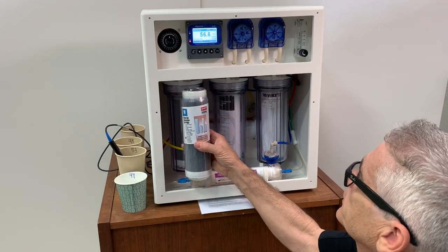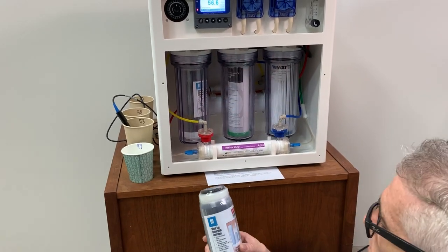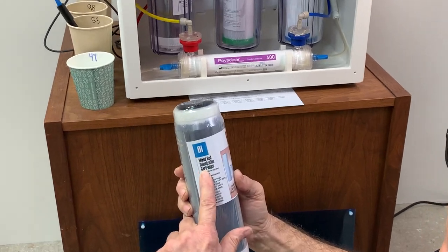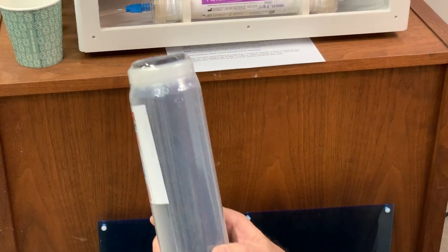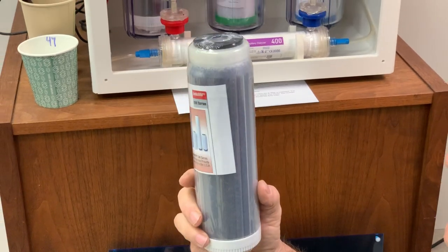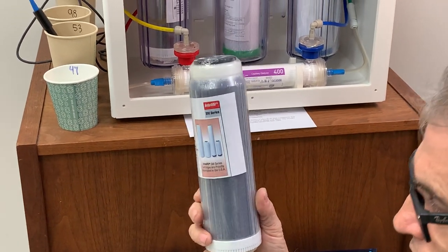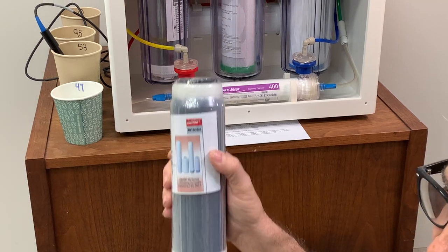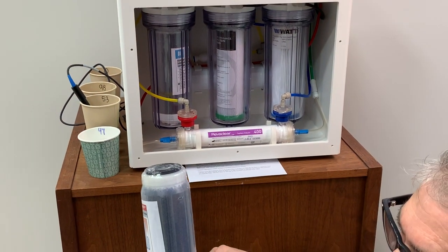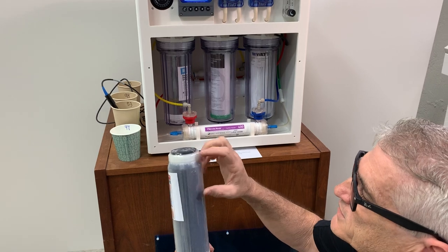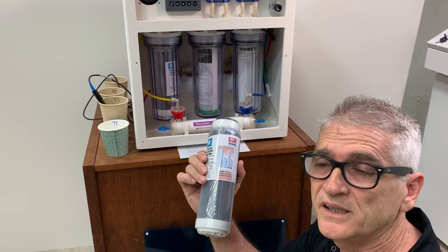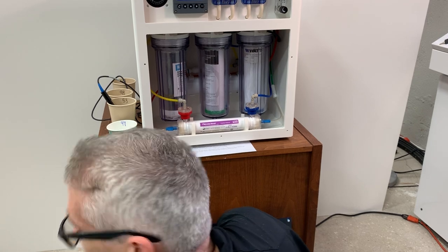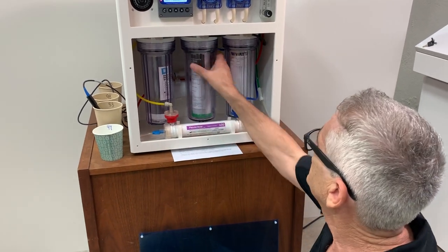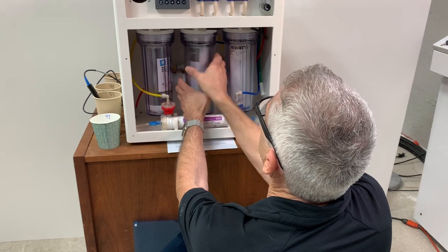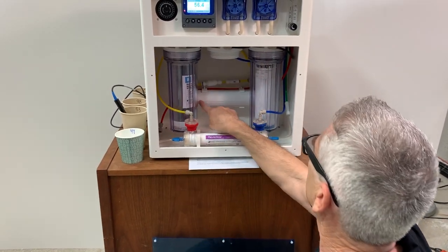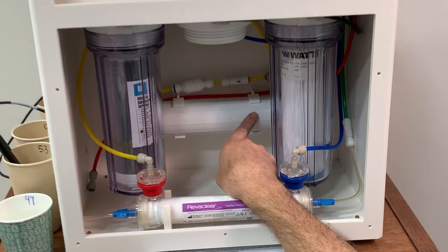The last filter on the hanging filters is a color changing mixed bed deionizing cartridge. So you're all familiar with how these work. As the solids get consumed within the DI, the resin changes color. So once this goes completely to brown at the top, you're going to start getting TDS in your water. That's total dissolved solids. Now behind these canisters, there is a 75 gallon a day RO membrane.